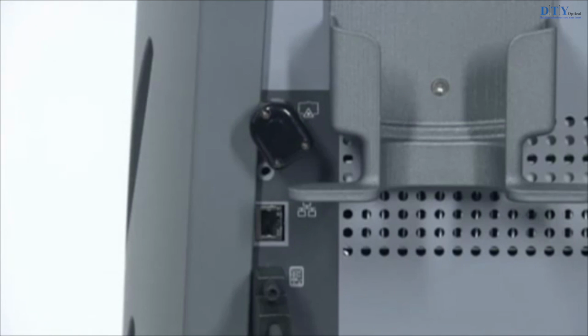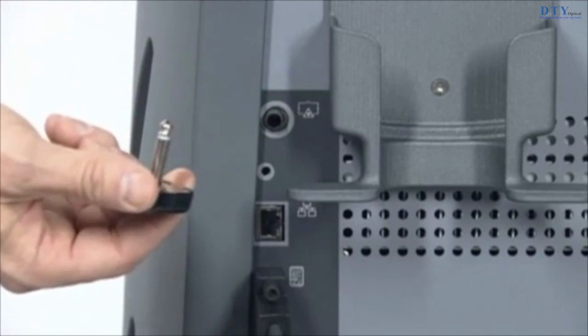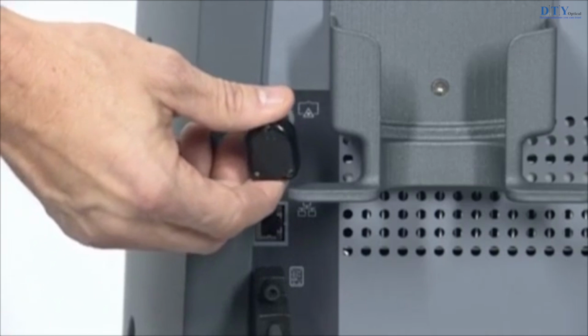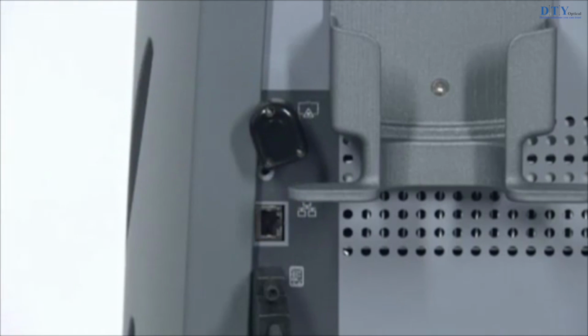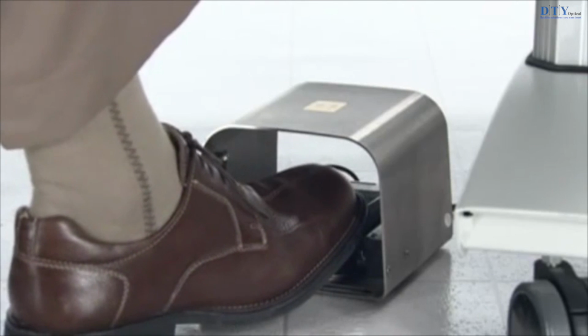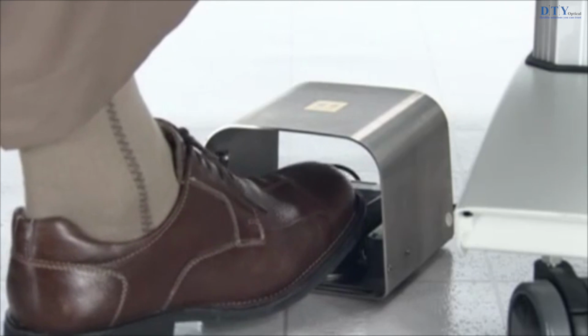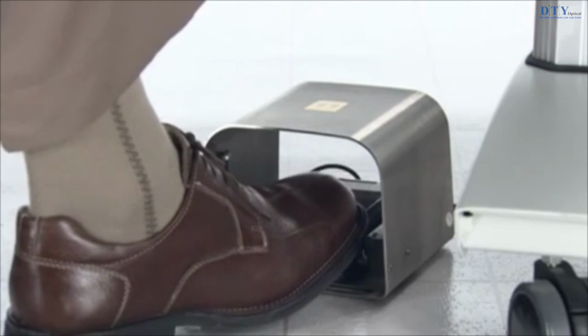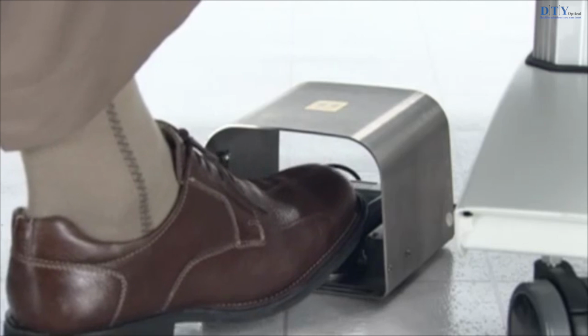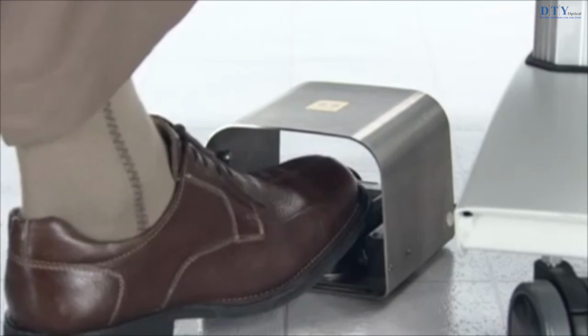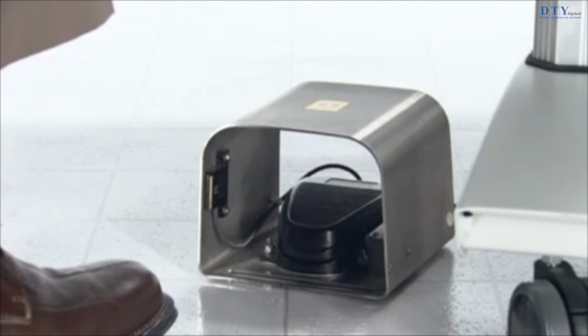The external door interlock plug must be inserted into the external interlock receptacle on the rear of the laser console for the laser to operate. The plug may be wired to an external switch to disable the laser if the treatment room doors are open during treatment. The foot switch activates the laser treatment beam when you depress it while the laser is in ready mode. If you are using the smart foot switch, the foot switch engages the automatic eye safety filter when you place your foot inside the foot switch housing while the laser is in ready mode.